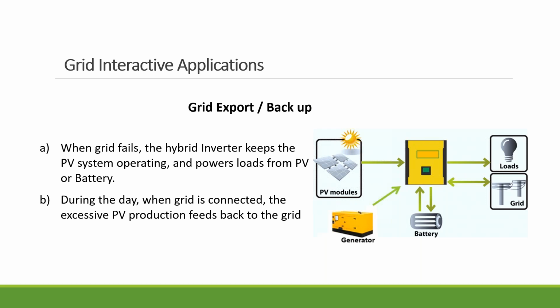Now, in most parts of the country, the utility is going to allow you to feed back excessive power from the PV. So you can set up your system so that during the day, when it's connected to the grid, you can push the excessive PV production back to the grid and get on net metering. And then in case of a power outage, it will disconnect from the grid and act like an off-grid system to power your essential loads, like important circuits. You certainly can also do whole house backup if you have enough budget for that, but in most cases, people will just back up those essential loads.